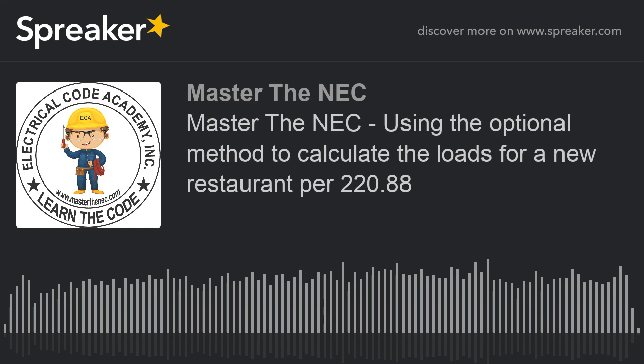Select the one demand factor that applies from the table, then multiply the total connected load by this single demand factor. The last part is what can mislead people; you could probably have left it off and it would be pretty intuitive. But we're going to work through an example.